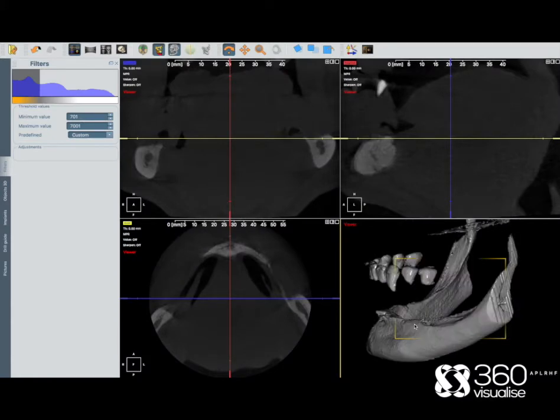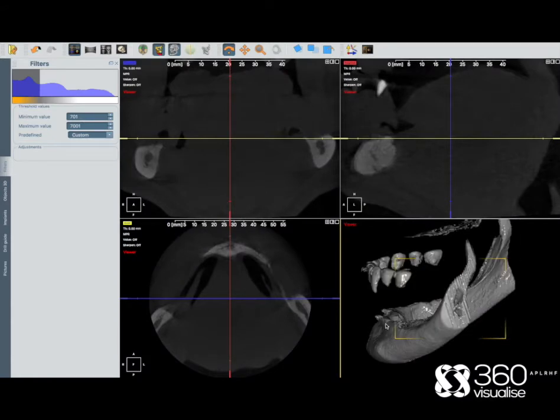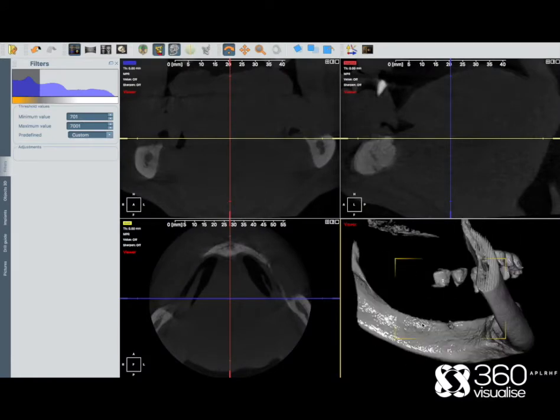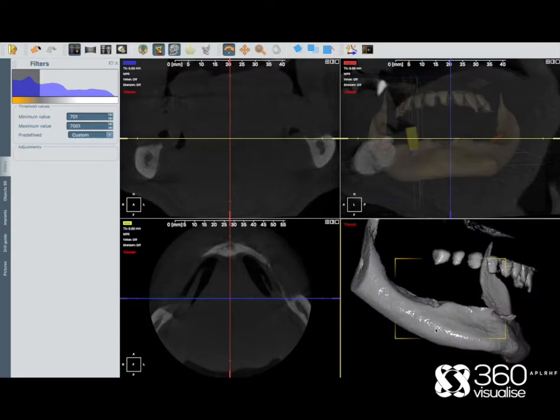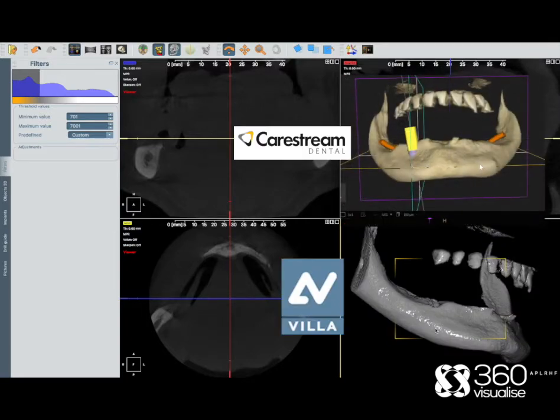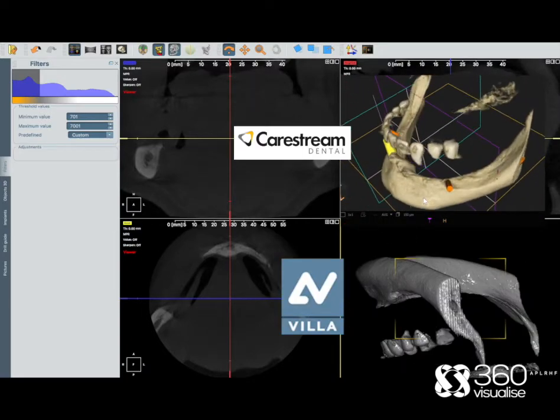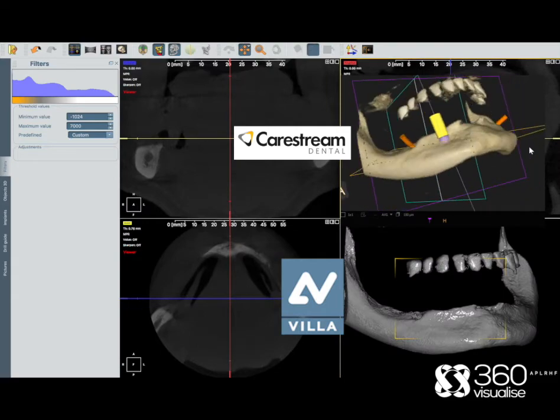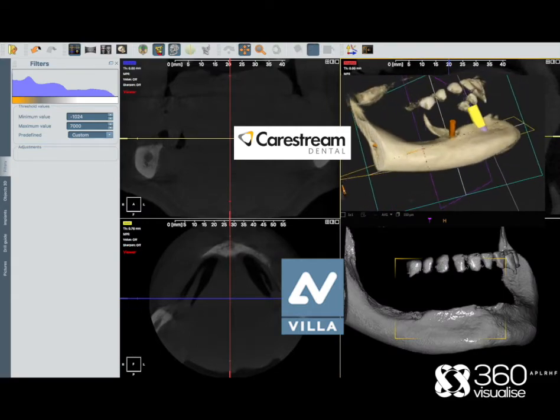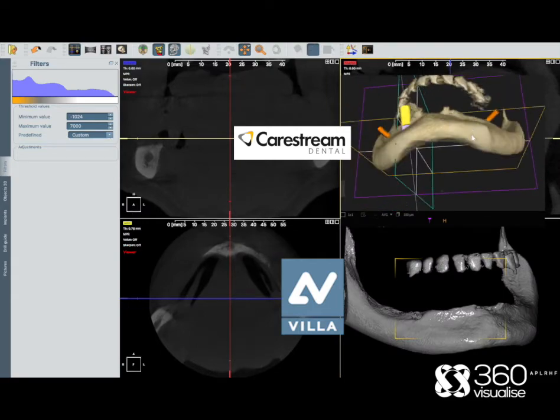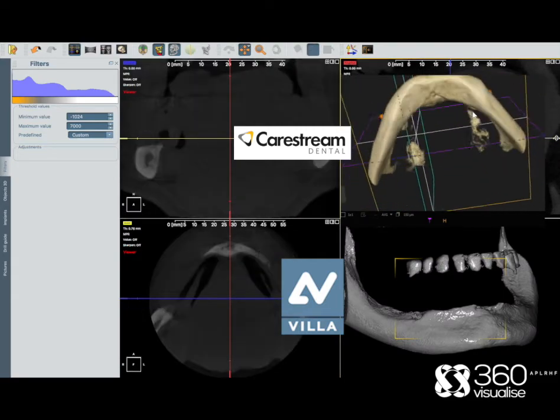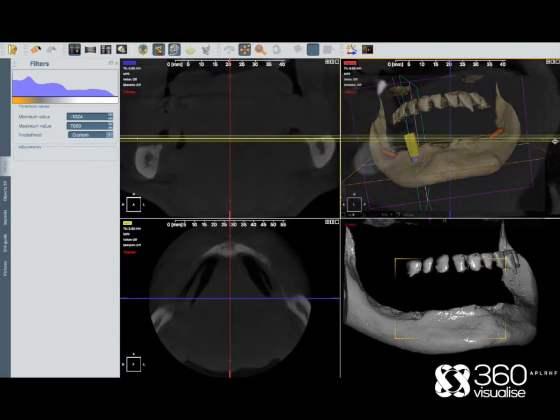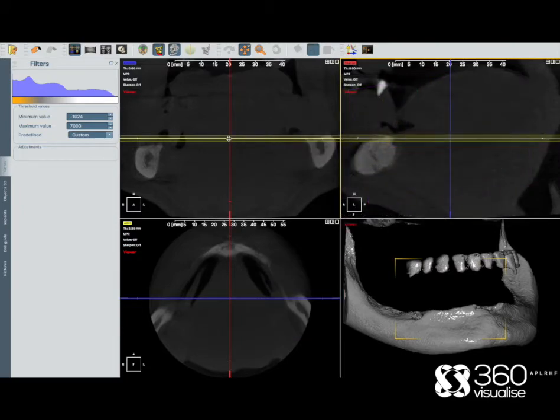Let's have a quick look at the 3D render. Down here in the bottom right hand corner we've got the Rotograph in grey. As you can see it's quite jerky — I'm moving the mouse very smoothly but I'm getting a jerky image. If you compare this to the CareStream in the top right hand corner in colour, it moves very fluid, whereas the jerkiness of the Rotograph could make it very difficult to navigate around the scan.